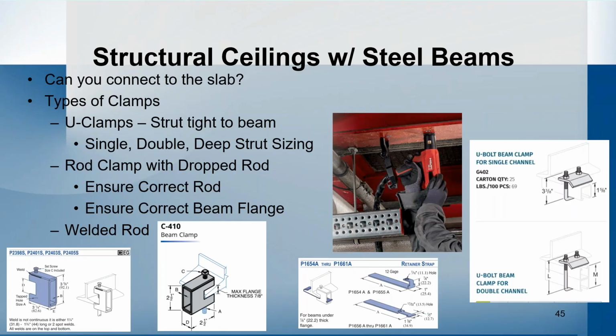The manufacturers have some different requirements. If you have a large clamp that's required, then you might need to use this piece, the retainer strap shown on the bottom there, to be allowed to use that larger type of clamp. And then finally, this is relatively new that Hilti came out with: a welded rod that gets directly welded to the underside of a steel beam, and then the rod is able to be hung directly from that.